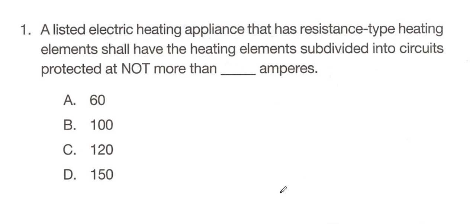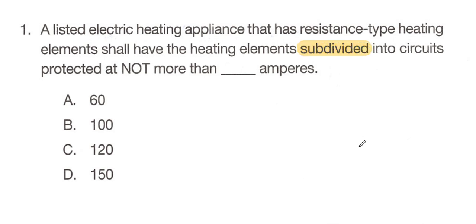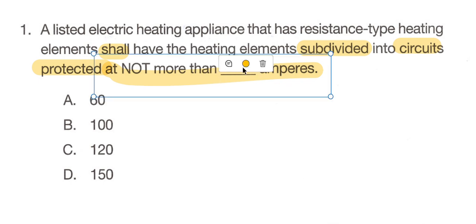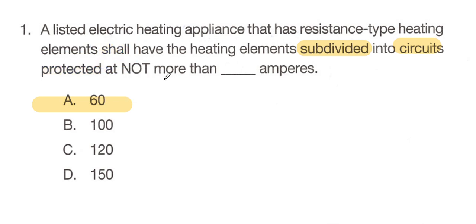Article 422.11(F) covers electric heating appliances employing resistance type heating elements rated more than 48 amperes — and all the answer choices here are more than 48, so we're still in the right direction. Continuing to read: each subdivided load shall not exceed 48 amperes, and each subdivided load shall be protected at not more than 60 amps. It says word for word "not more than 60 amperes." So A — 60 — is our answer.